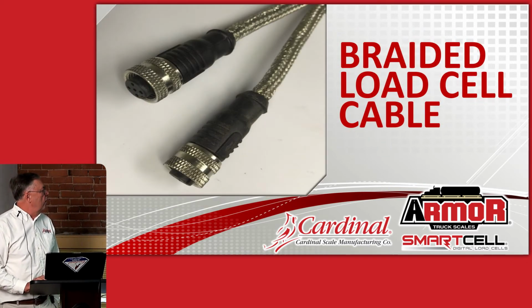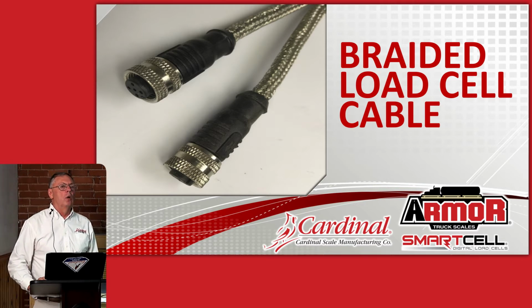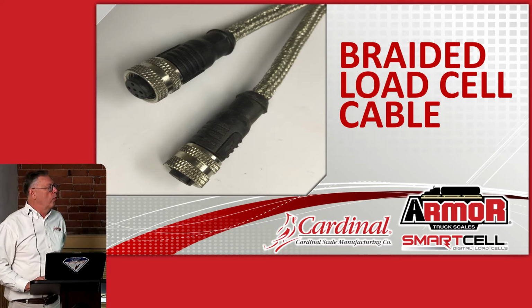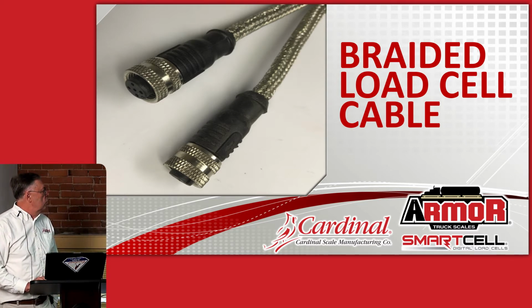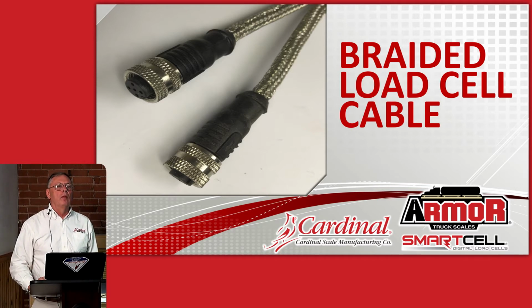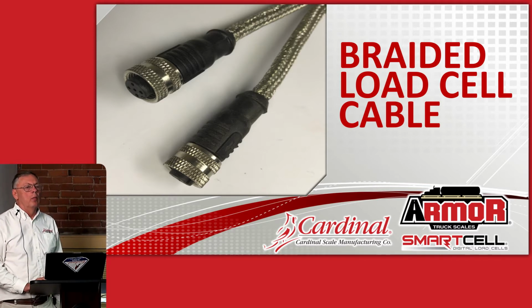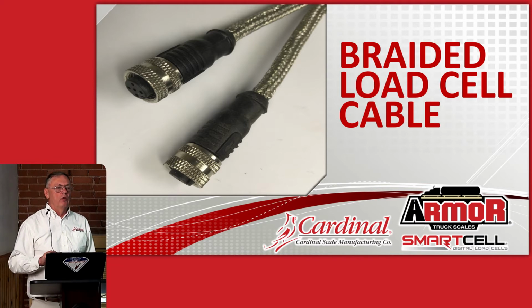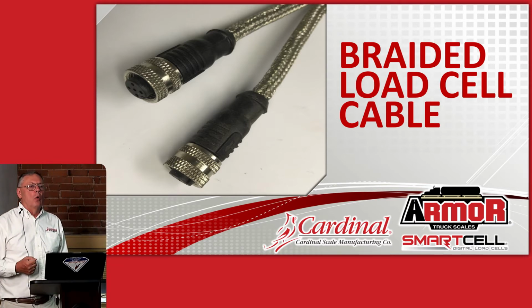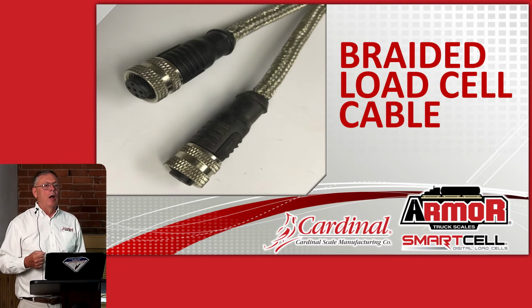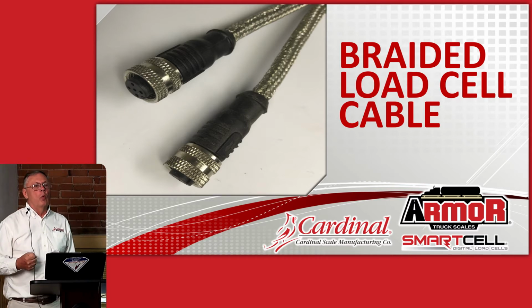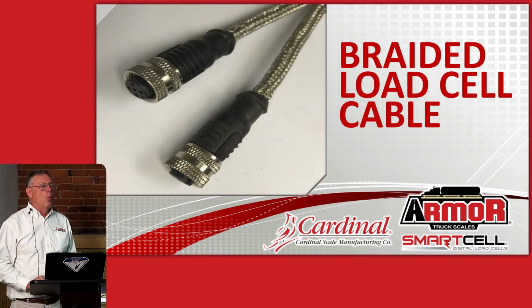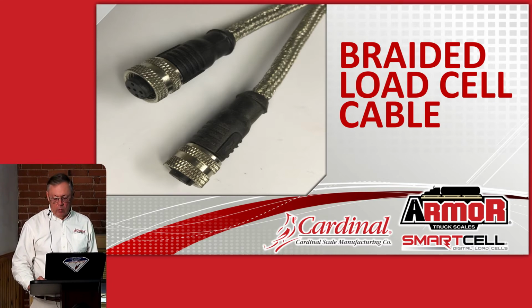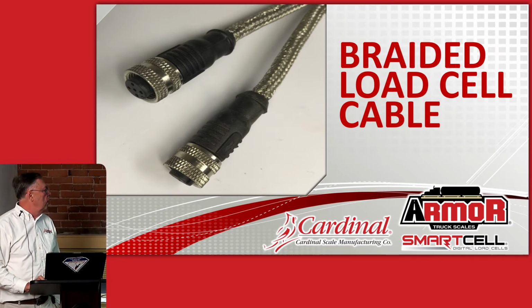This is a photograph of our new braided load cell cables. They're waterproof and double O-ring. They should stand up to service for many, many years before one of those would have to be changed out. Normally, the cause of failure of a load cell cable is either abrasion because of the cable moving in the weighbridge, or rats, mice, rabbits, and squirrels chewing on cables. And with the new woven stainless steel cover on there, those kinds of problems should be eliminated.